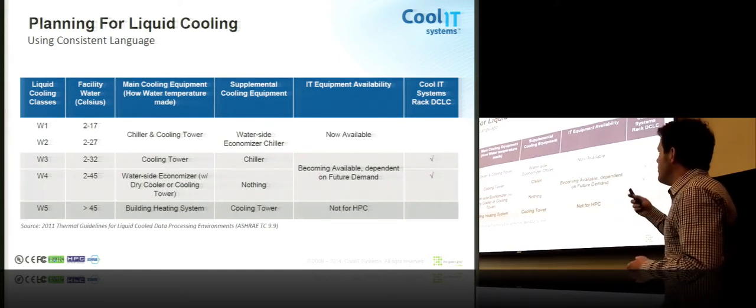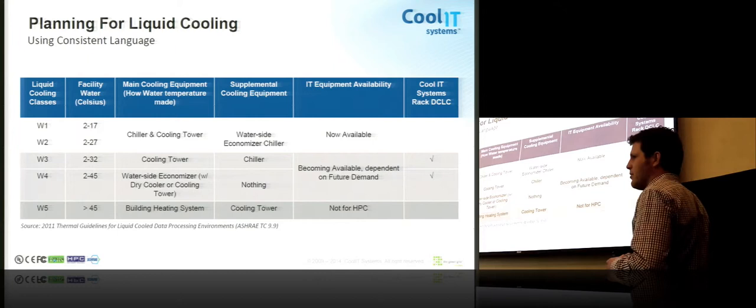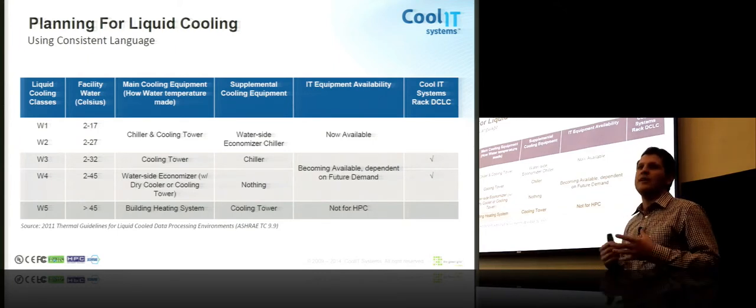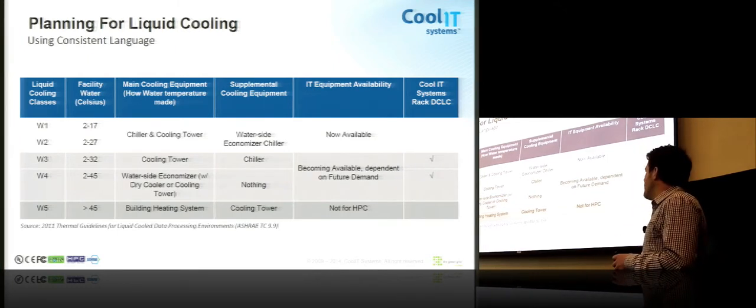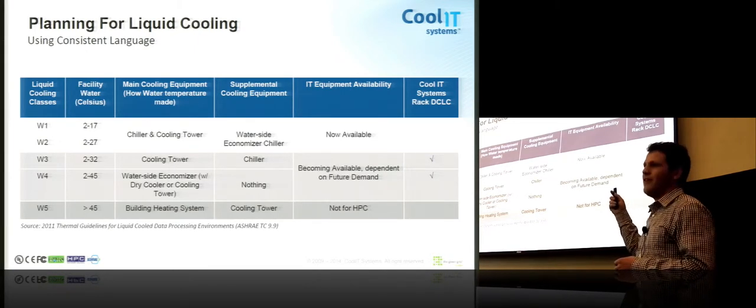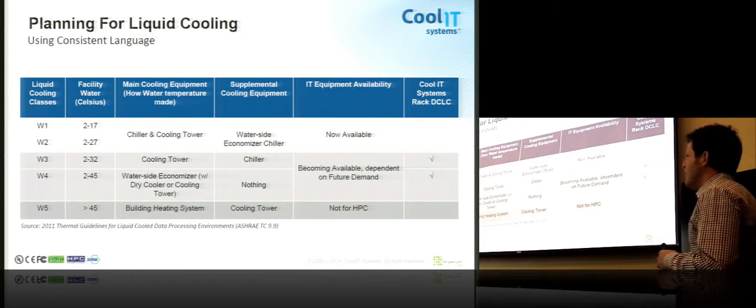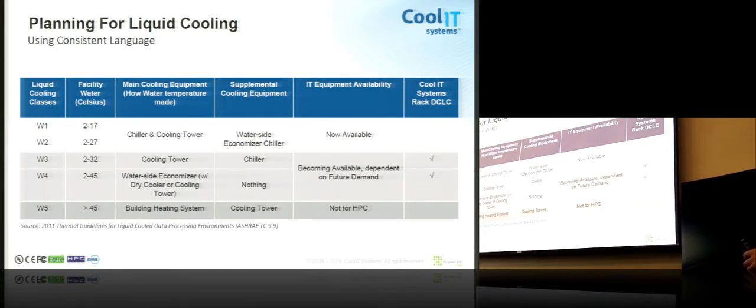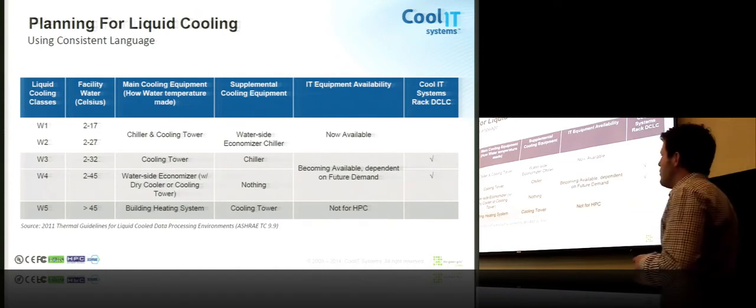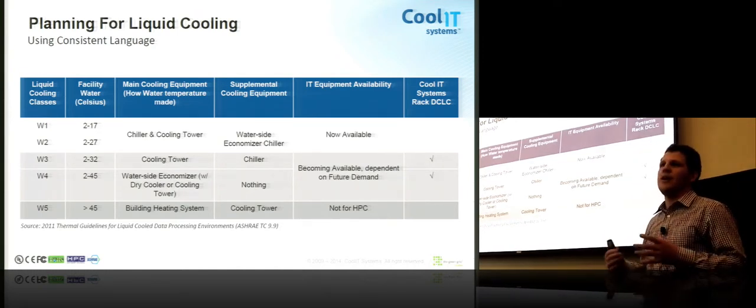More often though, W2 water is produced by a cooling tower with a chiller assist. W3, W4 water is where it really gets interesting and where we see quite a bit of savings for the data center. At W3 you can use a cooling tower almost, I'll say the entire year, very high percentage of the year. It's going to be 80% plus in most North American environments with some chiller assist. W4 we can use a dry cooler almost anywhere in the world year round.